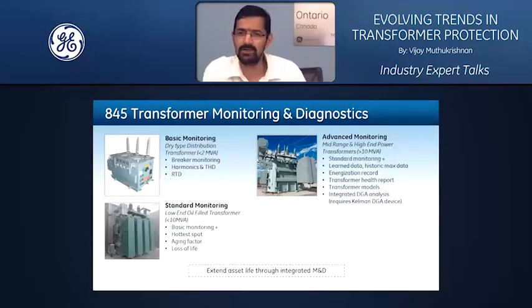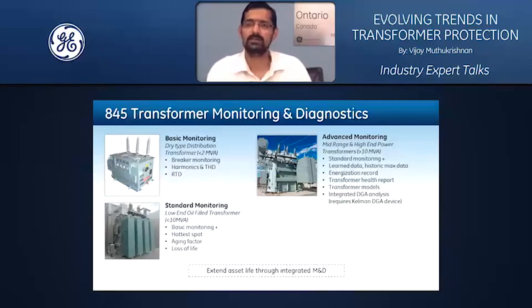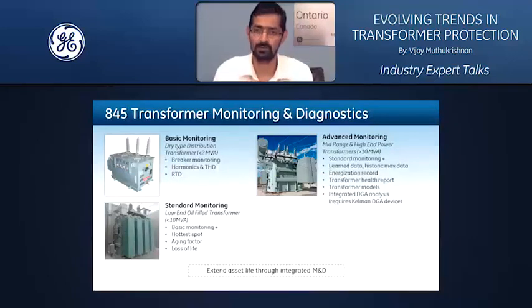This is one level. If you go up slightly to the next level, the IEEE and IEC standards define how you can calculate internal parameters of the transformer, such as hotspot temperatures, interpolated age of life, aging factor, loss of life, and harmonic derating factor type of parameters. Adding this type of thermal analysis becomes the second level of monitoring that you can do in any transformer protection relay. At most, you would have seen this much in the past in any transformer protection relay.